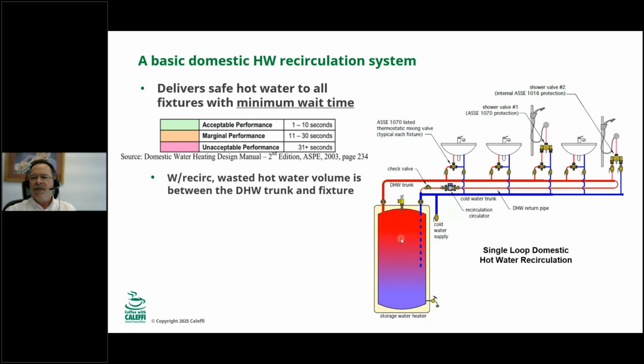So when we look at this diagram, we have our hot water supply coming here in the hot water trunk. That trunk goes out, and then in this particular single loop recirc schematic, it just shows a limited number of lavatories and showers. We'll get into some multi-branch recirc loops here in a minute. So then that recirculated water comes back via the recirculation circulator and then back to the hot water source. So in general, I just want you to understand what these schematics are trying to tell us here. Now this one, we show ASSE 1070 and ASSE 1016 scald protection valves at each point of use. So that may or may not be required, but in this particular schematic, we do show them.